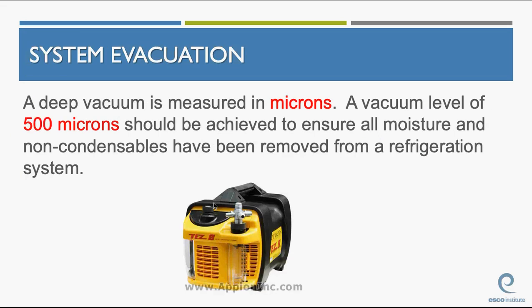Okay, a deep vacuum is measured in microns. A vacuum level of 500 microns should be achieved to ensure all moisture and non-condensables have been removed from a refrigeration system. 500 microns is how you remove all moisture. Very deep vacuum. The water will boil off at like negative 20 or 30 degrees. I mean, your boiling point drops way down in a vacuum. Water will just boil, so will any other liquids in there. Do not start a compressor while you're in a deep vacuum. By the way, that's a vacuum pump in front of you there in the picture. Those are awesome.